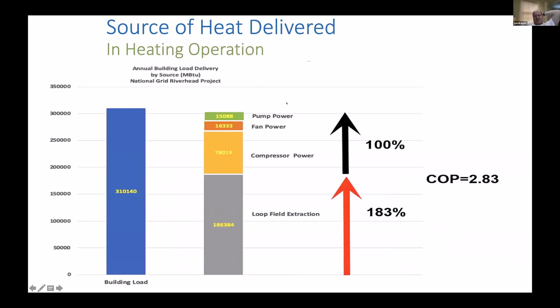Here's another way to explain that. So this is heating operation. This entire neighborhood was using 310,000 MBTUs, but only 186 of those 310,000 come from the loop field. This was the compressor power, this was the pumping power, and this was the fan power. So the total energy use of the system was approximately 310,000. And if you then look, the COP of the system on average was about 2.8. Not really the greatest, but I think they learned a lot on how to make this more efficient. And a lot of this was due to much higher pumping power in that system design.